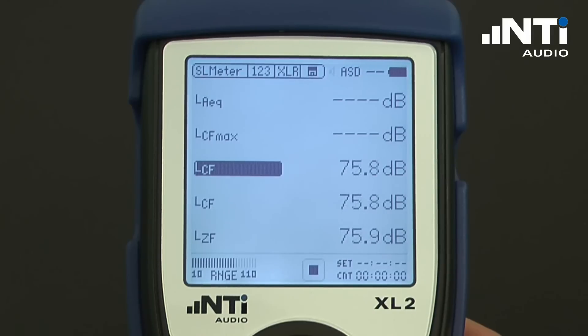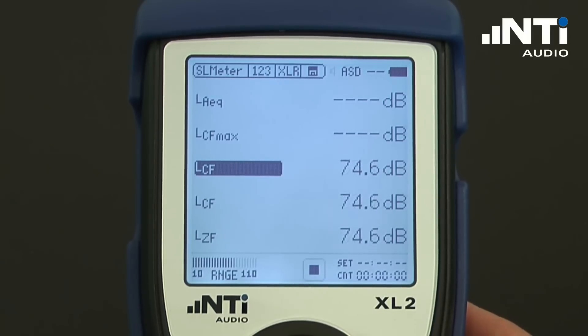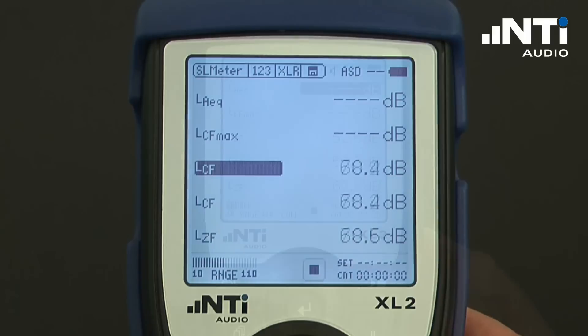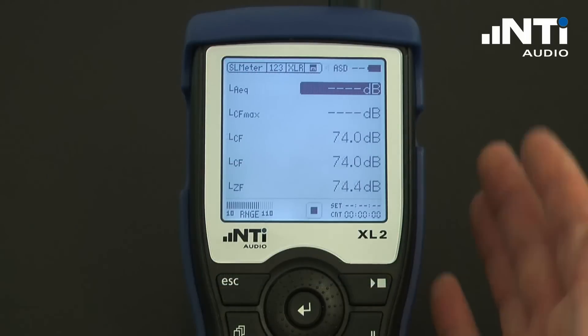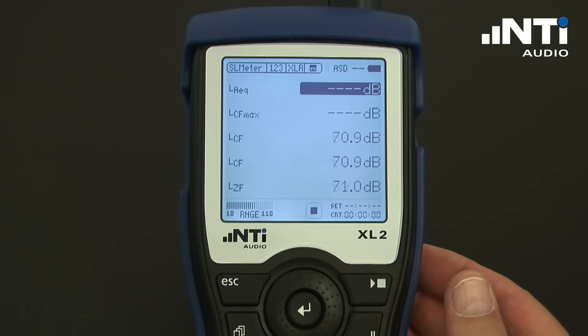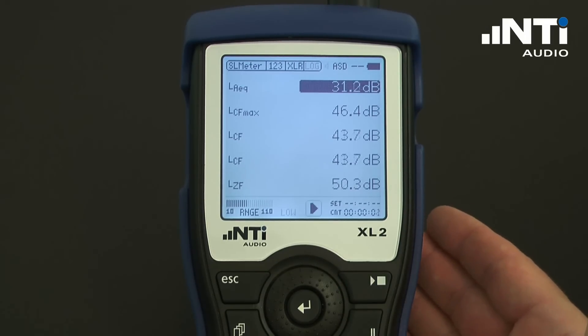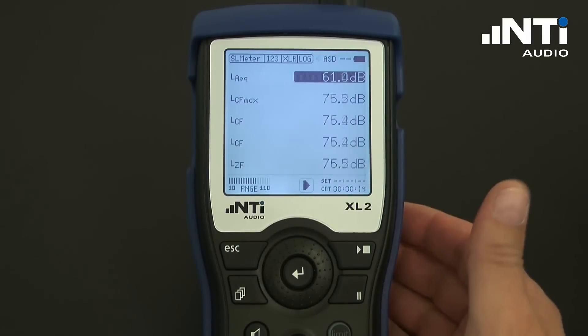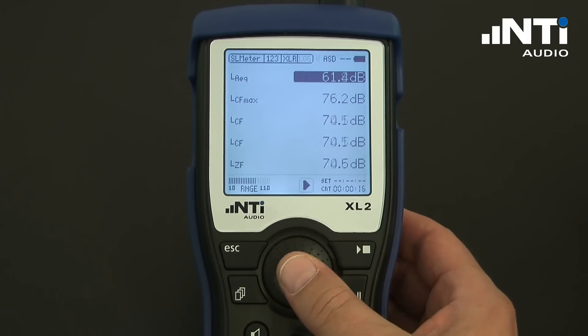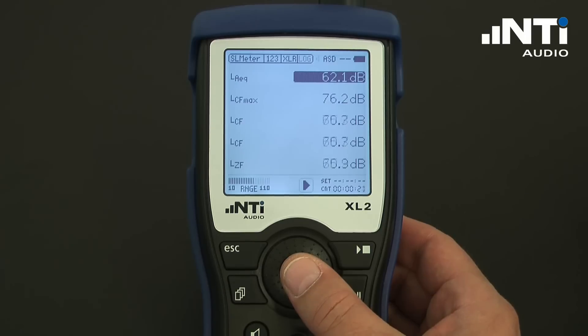Under any conditions, the XL2 measures all values in parallel. The user can choose which results he wants to have added to his screen and at what size. Averaged values are not yet displayed as the averaging needs to be started first with the start button. The size of the measurement results can be altered by pressing enter on the measurement value, and it toggles between normal, bold, and x-large characters.